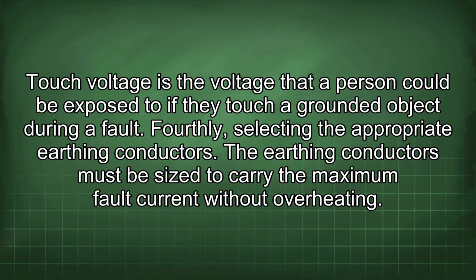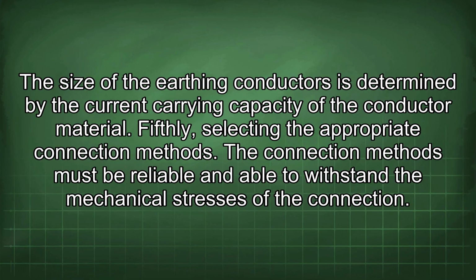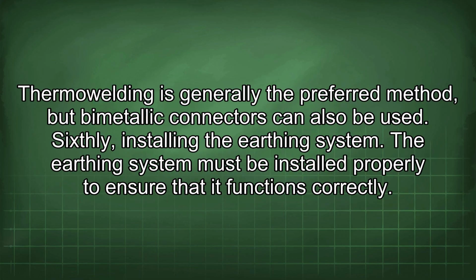The earthing conductors must be sized to carry the maximum fault current without overheating. The size of the earthing conductors is determined by the current carrying capacity of a conductor material. Fifthly, selecting the appropriate connection methods. The connection methods must be reliable and able to withstand the mechanical stresses of the connection. Thermowelding is generally the preferred method, but bimetallic connectors can also be used.